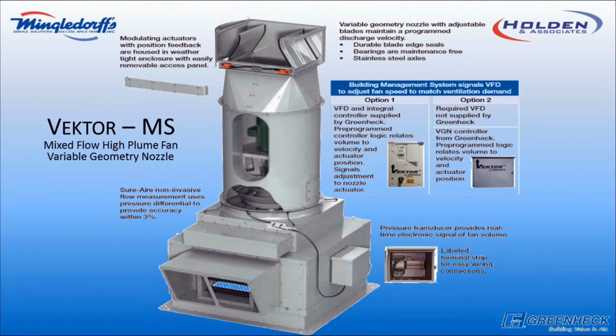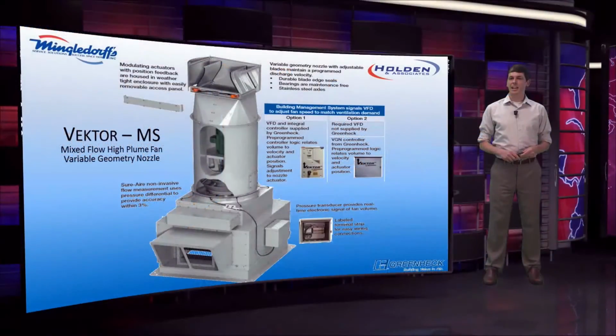Now this image will show in detail the different components of the variable geometry nozzle and everything that is occurring. Everything from the modulating actuators, moving the variable geometry blades, to the Sure Air non-invasive piezo ring that's connected to a pressure transducer as an airflow measurement, which can then signal to the Vektor controller what is going on in terms of airflow. There are two options that Greenheck can do. We can provide a VFD that's connected to the controller, or if the customer prefers, we can connect it to a VFD by others.